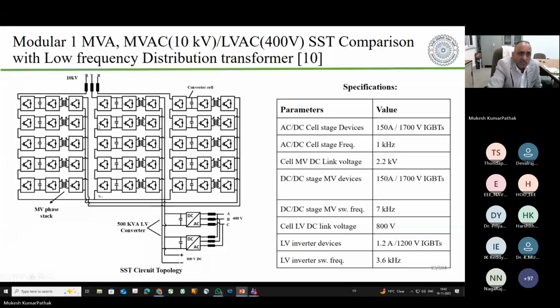DC output. Similarly, for the second phase, you have DC outputs coming from all 5 modules, and they are also connected in parallel. The third module also similarly gives DC outputs which are connected in parallel, and all 3 DC outputs are connected in parallel to form a DC link. So this is the low voltage, LV DC link.